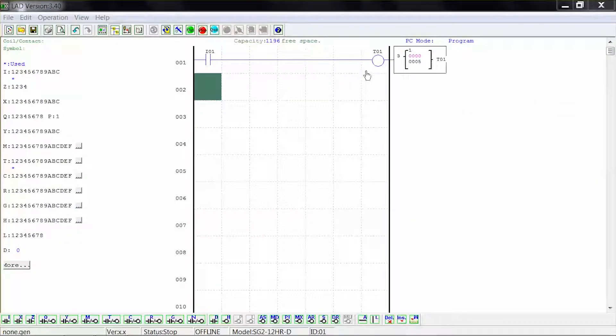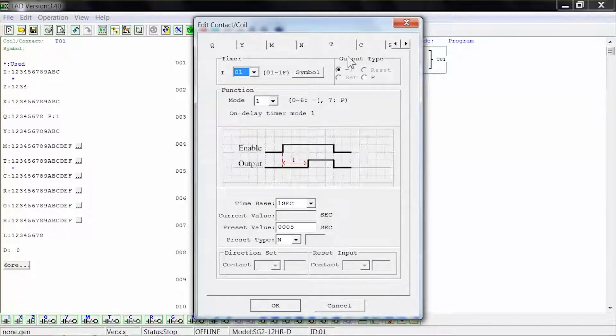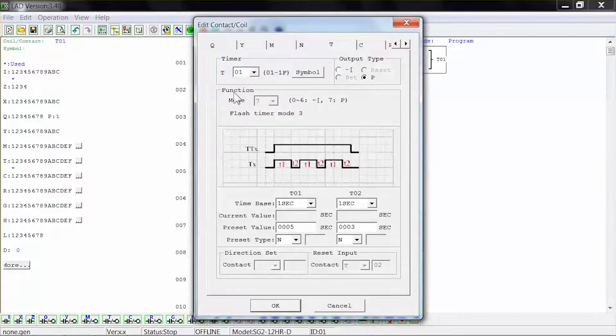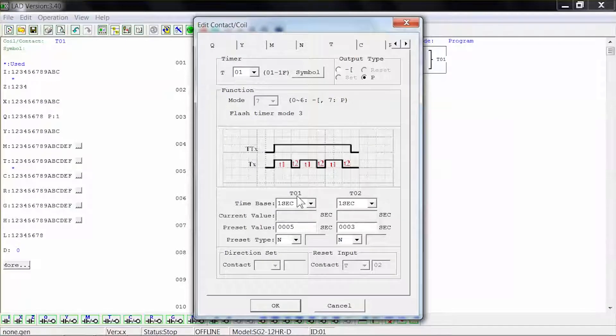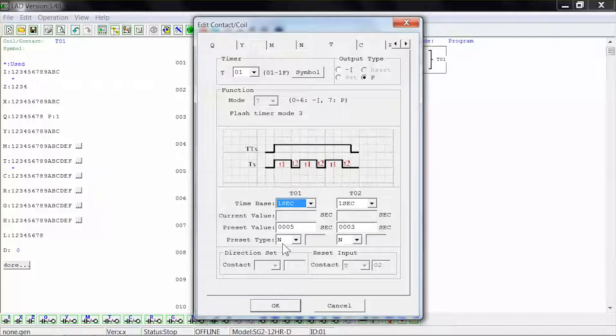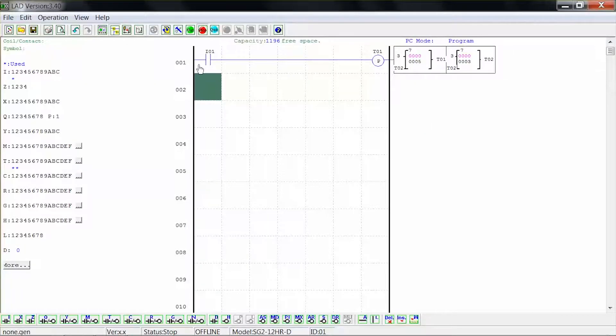For the next example, double-click the timing coil to open the edit coil window and select output type to be P. Note that the function mode is locked to number 7, which is a flash timer version 3. For T01, our first timing function, select time base to be 1 second and preset value to be 5 seconds shown as 0005, with preset type N for numeric constant. On the second timing function T02, select time base to be 1 second, preset value to be 3 seconds shown as 0003, and preset type N for numeric constant. Click OK to close the window and click run to start the simulation.